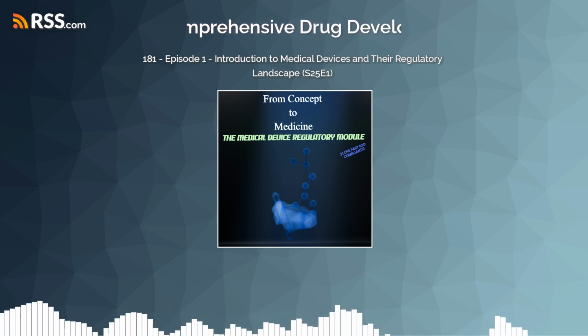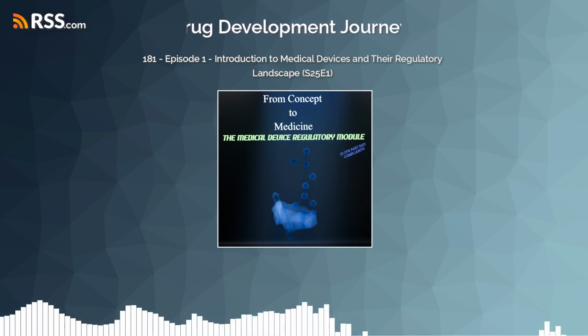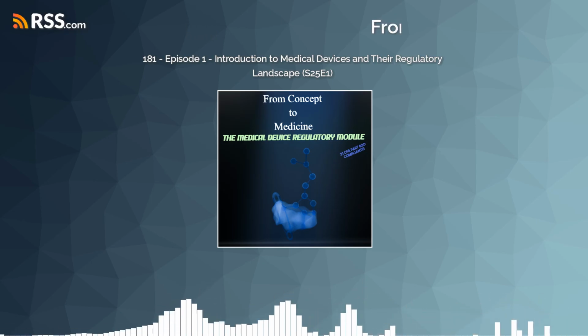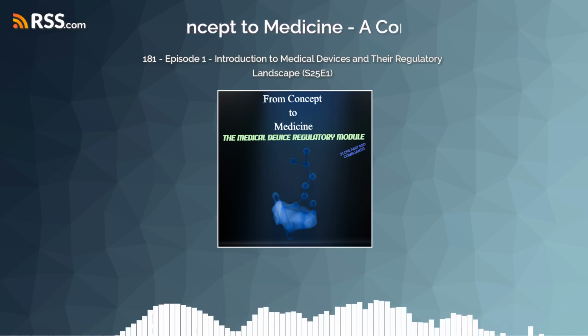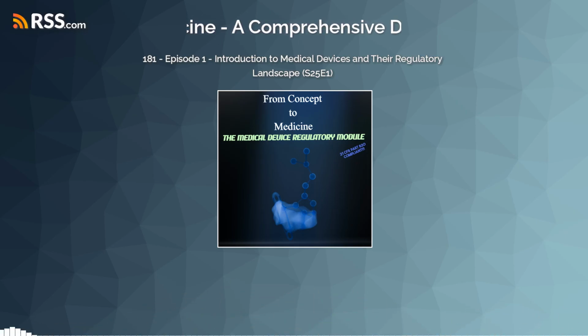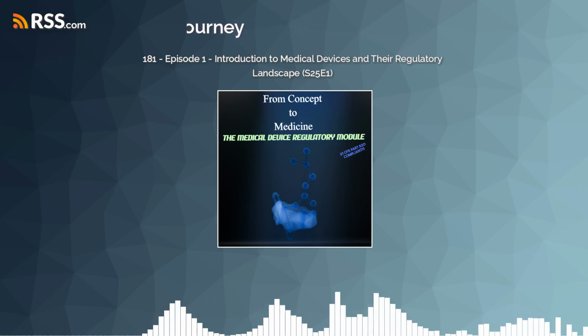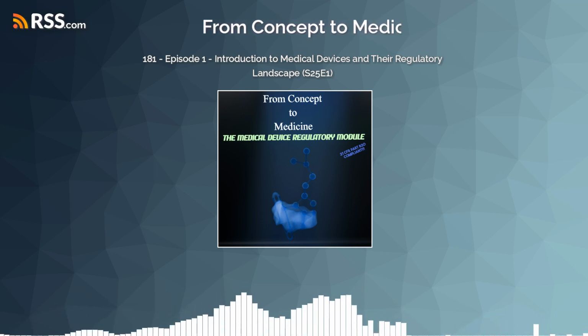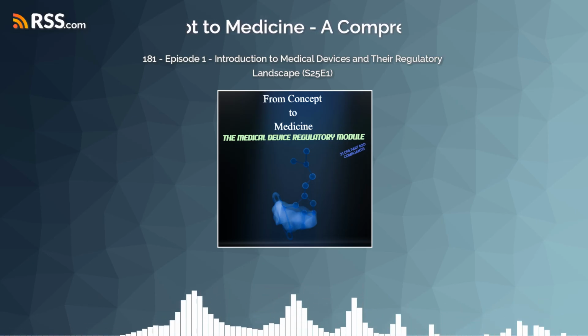And what about the pre-market review process itself? What's the main difference there beyond the notified body versus FDA staff aspect? Under the EU MDR, for most devices above Class I, the notified body review focuses heavily on the manufacturer's technical documentation, proving the device meets safety and performance requirements in their quality management system, often including that ISO 13485 audit. The emphasis is really on ensuring the manufacturer can consistently produce a safe and effective device and verifying the clinical evidence supporting it. Consistent production and clinical evidence. Yes, and the EU MDR significantly increased the requirements for clinical evidence for almost all devices, even established ones.